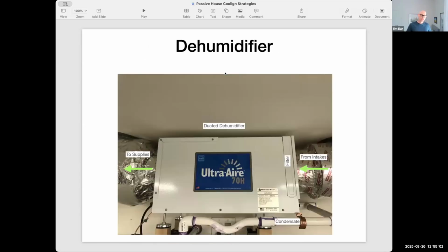The 800-pound gorilla in the room is humidity, especially in buildings with a tiny cooling load left. You might have a dehumidification load you want to get on top of, and beyond the earth tube or earth loop we discussed, the way to do that is with an active dehumidifier to top it off. But I'd say these are the equalizer, the last thing you go to, not the first, which is common practice now.